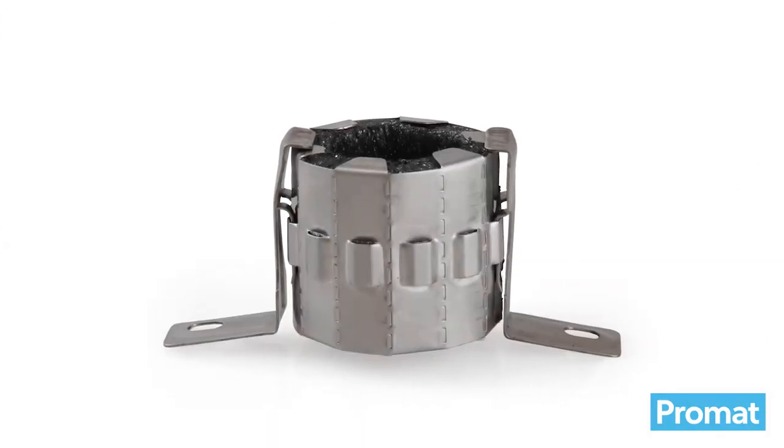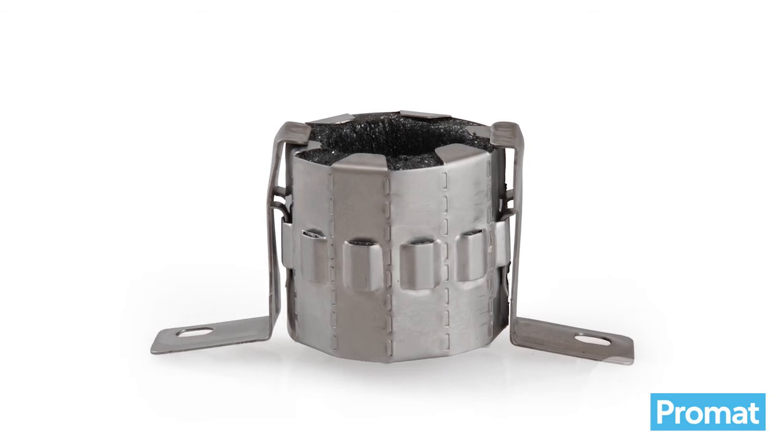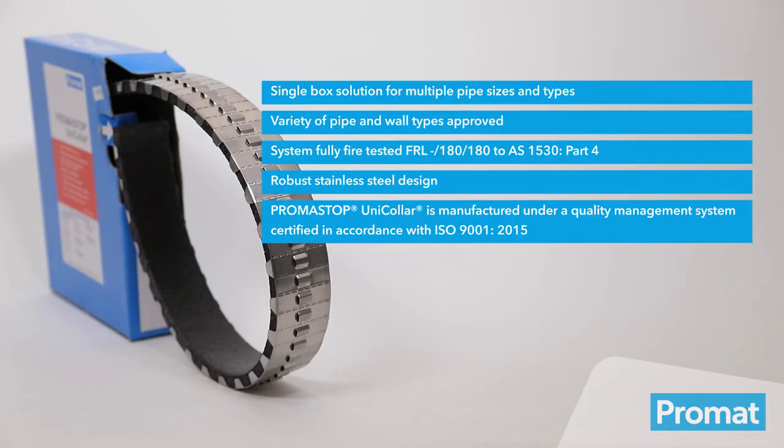For smaller pipes — 32 millimetres and below — the collar is available in a pre-made form known as PROMASEAL Conduit Collar. A universal collar for multiple pipes, multiple sizes, multiple approvals — a must-have for plumbers, electricians and passive fire installers.